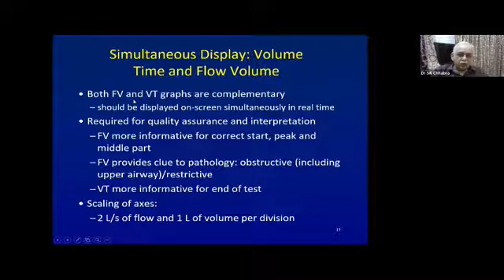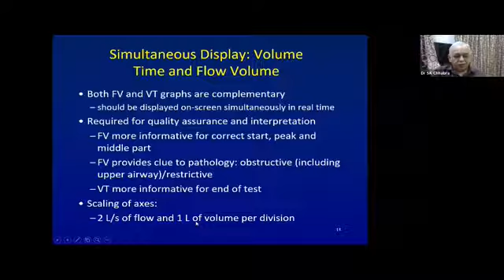And the shape of the flow volume curve provides important clues to pathology because the shape changes with obstructive or restrictive pathology. So one can get some impression from visual inspection of the flow volume curve as to what kind of pathology the patient may be having. The end of the test, on the other hand, is picked up better on a volume-time curve. So both tracings are complementary and both should be obtained. A good machine is one which gives you both displays, in printout as well as on the screen. The scaling of axes is important, and the standard scale is that per division on the flow axis it should be 2 liters per second, and on the volume axis it should be 1 liter per division.